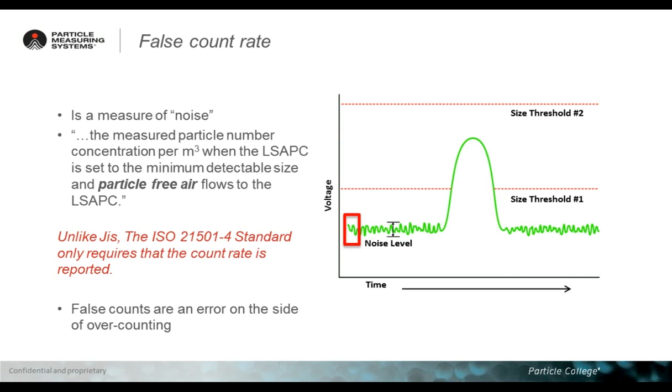Let's jump to the false count rate, or you can call it the zero count test, or even the measure of noise. This is really a measurement of noise, simply because any electrical system, any electronic board has a certain amount of noise generated by the power supply and electronic components that I will not bother you describing right now.